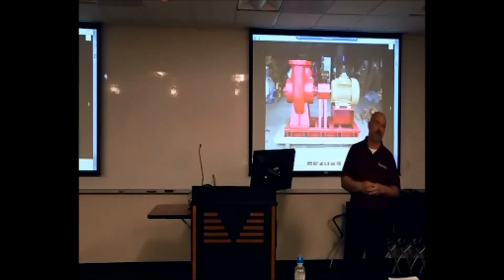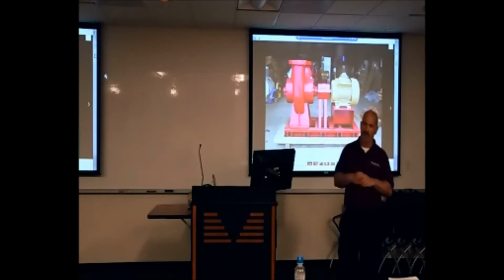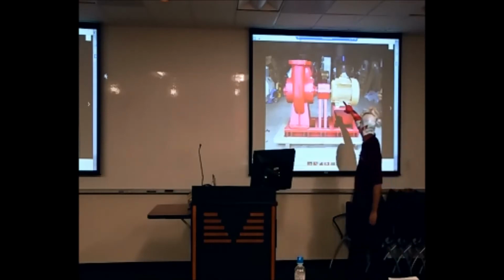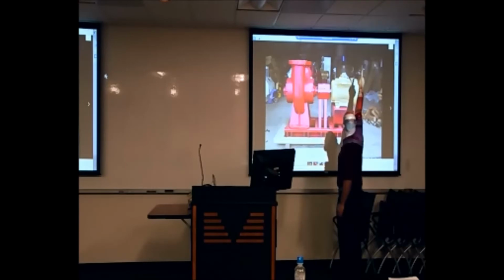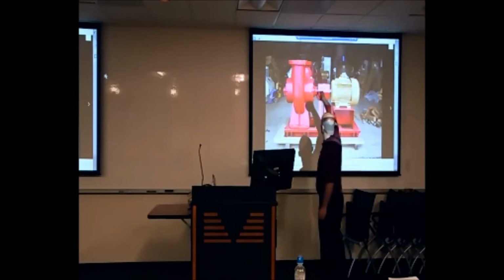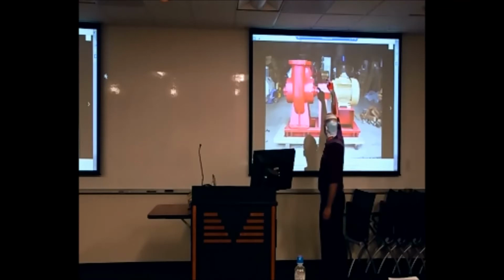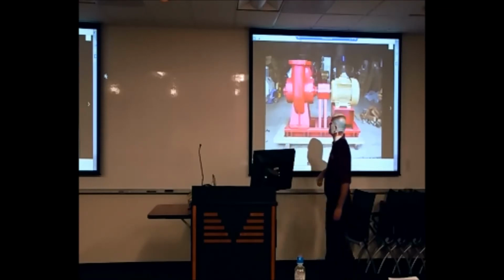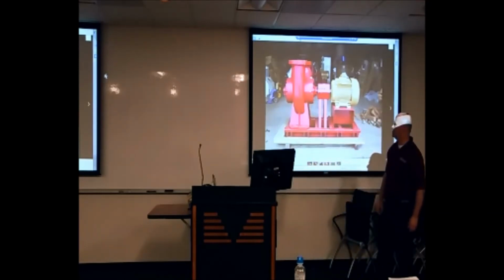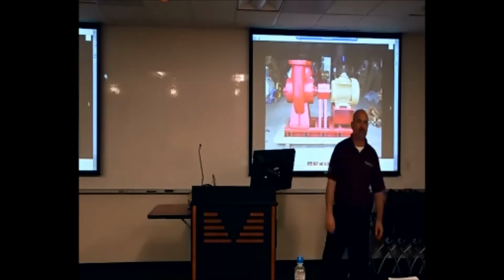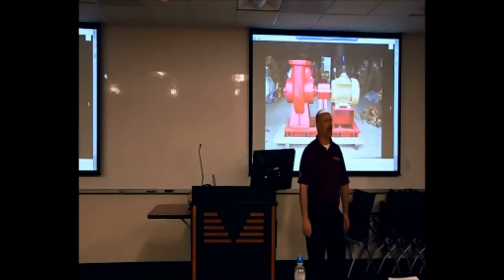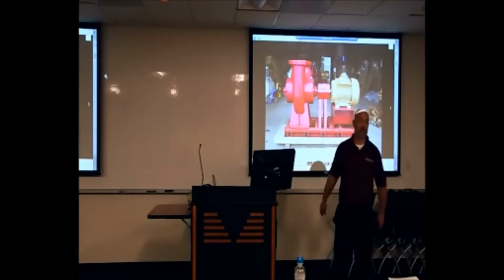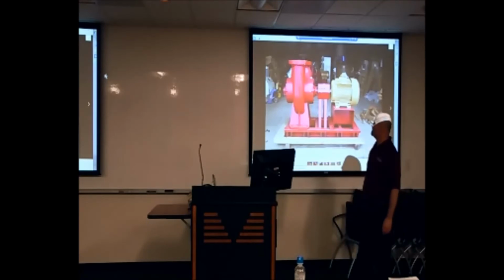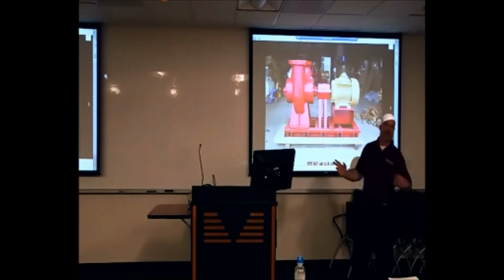Synthetic greases tend to last a long time, and we get considerable life out of the bearings with this grease. The zerks that are located on the front and back of the pump are usually located right at the top here, and there you can see a little red one right there, to allow you to grease those, as well as on the top of our bearing assembly here, and over here is going to be a zerk for those as well. Water is the biggest detriment to the bearings, not so much the greasing of those bearings. We find more than likely it's water that's destroyed a bearing, or, like we had discussed, an electrical issue destroying the bearing as well. Generally, I don't find an ungreased bearing unless it was a complete lack of maintenance, left the pump sitting there for 10 years and never did a darn thing to it.